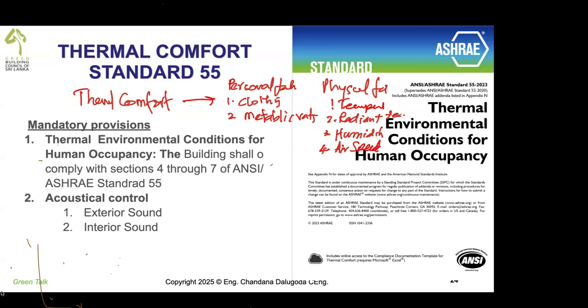changes your thermal comfort. Now this standard gives you thermal comfort as PMV, predicted mean vote. And by a computerized simulation program, we can check whether you're comfortable or not in a given space. So in green buildings, we'll have to do this computer modeling and see whether the occupants in particular spaces are comfortable or not. You have to prove PMV. Actually, that says PMV minus 0.5 to plus 0.5. This is the range you'll have to be in, and dissatisfaction 10% and below.